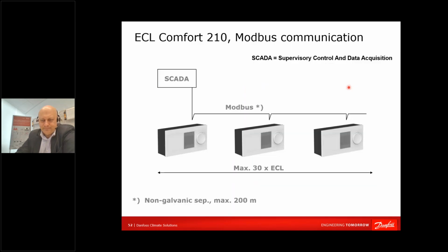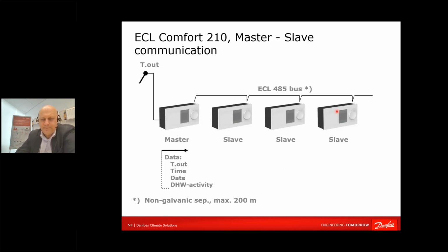So you can connect ECLs to supervision systems via Modbus, and you can transfer the data easily. We are doing it. You can even transfer to a SCADA system the position of a 3-point actuator. So you can see actually where a 3-point actuator is. Is it 20% or 70% open? That's a trick. If you are building a larger system, you need more circuits. You are not satisfied with only one ECL.